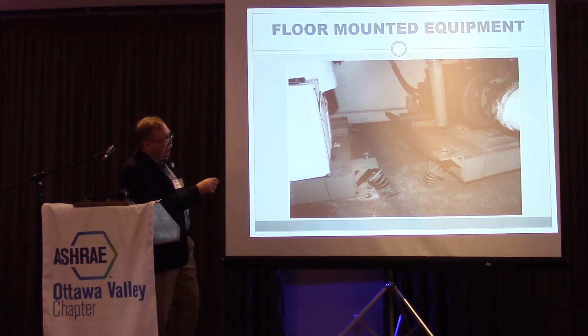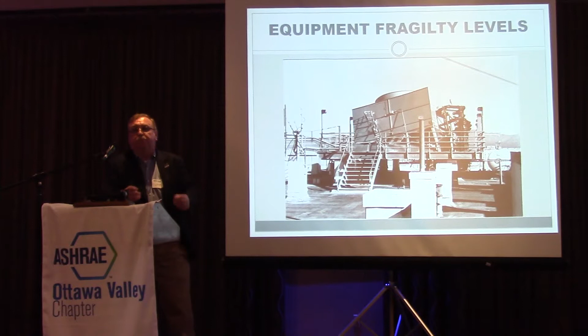This photograph is from the '62 Alaska earthquake, I believe. What you basically had here was the beginning of fragility levels of equipment—when should you start looking at the equipment itself and say that it can't be used in this area because it isn't strong enough for the seismic zone we're in. Here you've got a cooling tower, and as you can see, near one of the legs it's just a piece of formed angle. I don't know how thick it is, but it wasn't thick enough at this corner—it buckled, went down, and the whole rest of the tower came down around it.